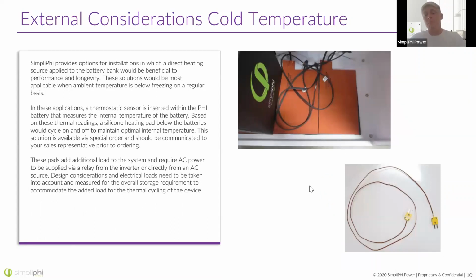Another option, for much more extreme climates where it's absolutely necessary, is a heating pad. Heating pads can add cost and complication to the design, but if there's no other way to keep the batteries warm, they're a great option. The batteries need to be ordered ahead of time with thermistors installed to sense the temperature. The heating pads are placed underneath the battery, connected to the battery thermistor, and then connected to the inverter for power. They run off the inverter, not directly off the battery, so they don't completely drain it.